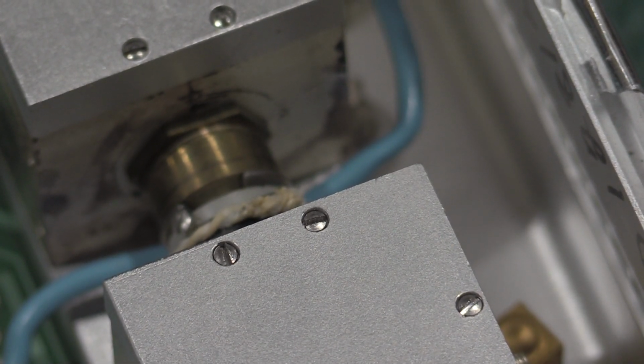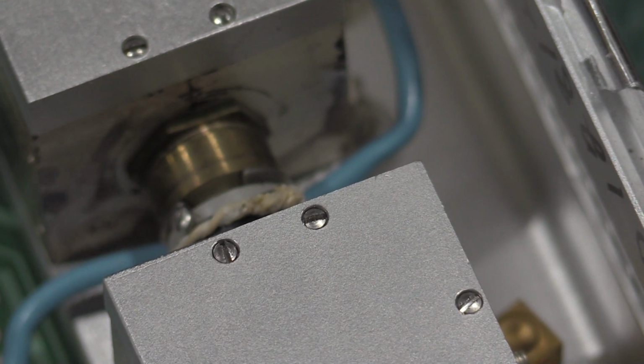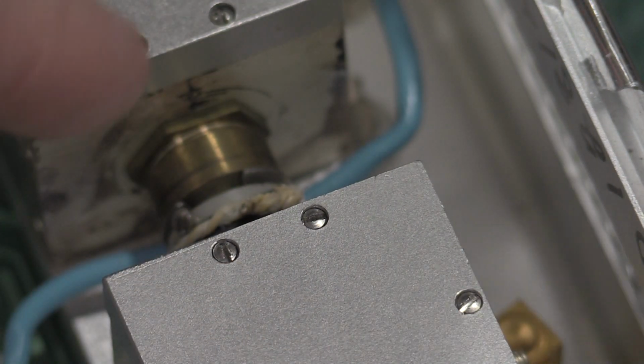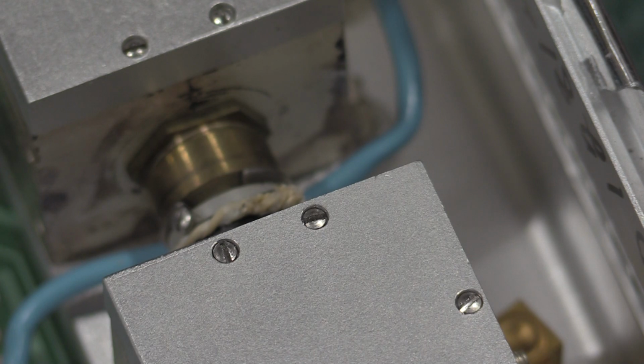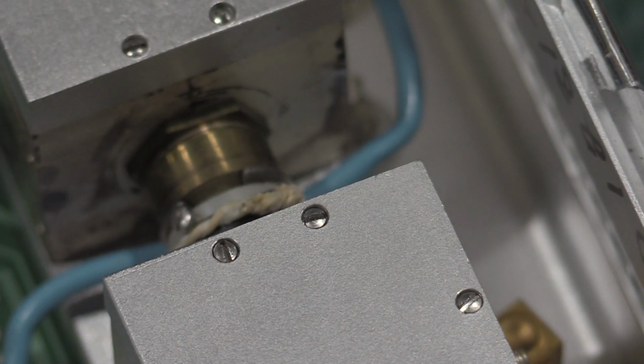So let me set up for the last step of the calibration, which is checking the flatness regulation. Hopefully this stays in and we can toss this one in the rack. If that cracks again and the high side stops working, I'll just take that coupler out and disconnect it completely and then just use the low side, because I can still use it on the low end. Yeah, this has been one crazy calibration. So I'll have to get us back up to this step, but I'll do that tomorrow, and then we will check flatness.